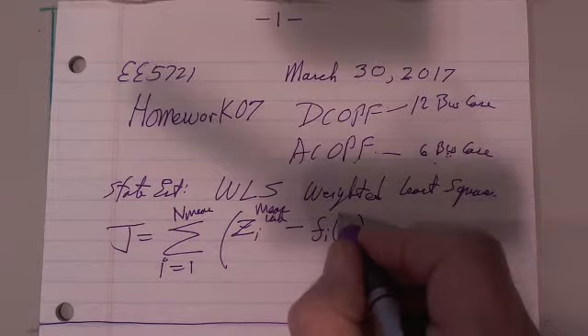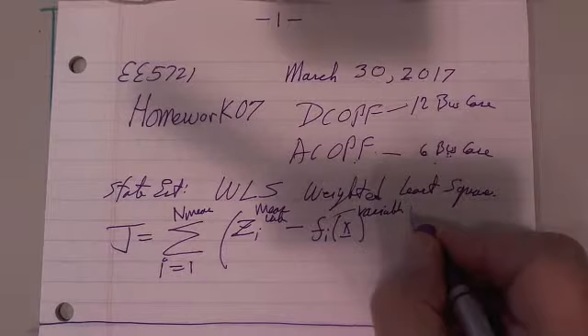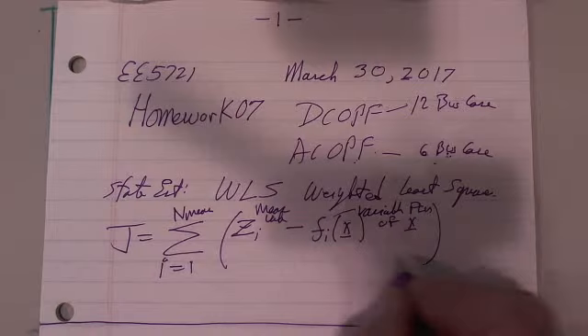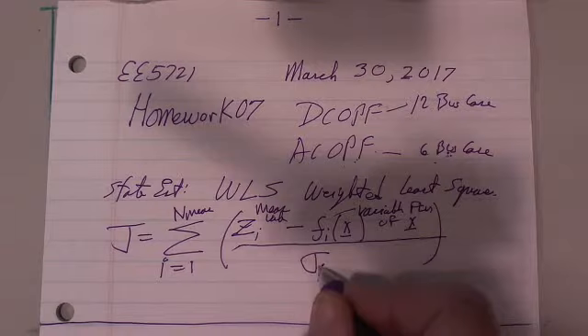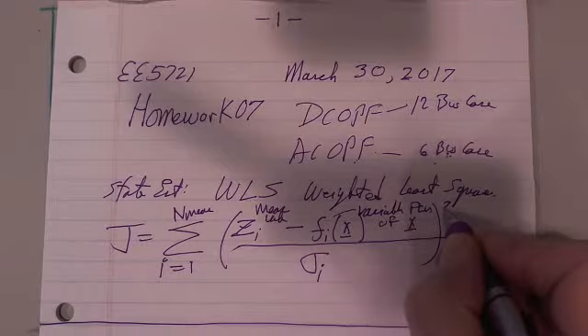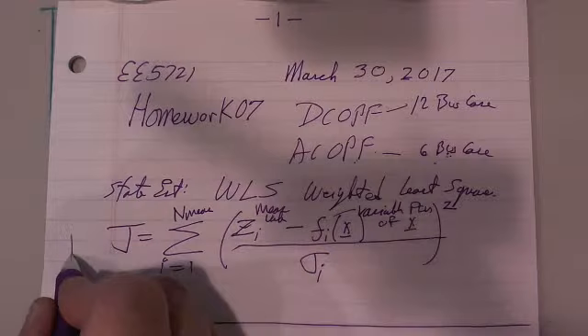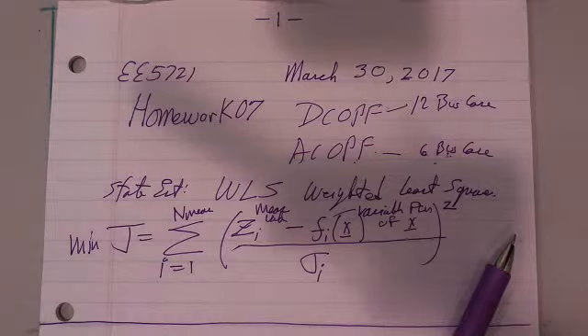That's our state variable, and this is the variable as a function of x, the state variables, and we divide this by sigma i, the so-called standard deviation for that particular measurement, and we square it, and that's what we end up wanting to do, is minimize this. And this was the first state estimator. It stood in good reputation for many years until.